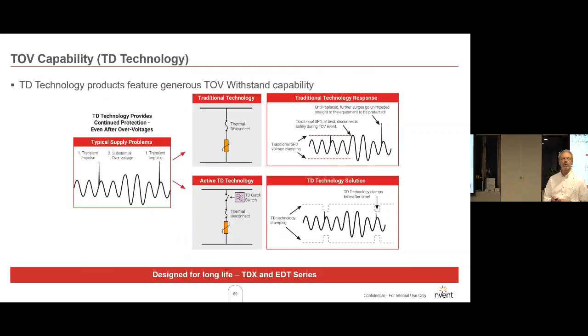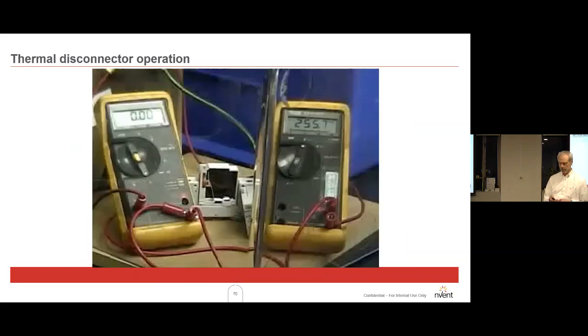We won't dwell any more on this today, except this was a slide showing one of the important things is thermal disconnect. So metal oxide varistors, when they get consumed, they'll go short circuit. So that's if a temporary overvoltage is there for a long time, or if they've just been working for a long time and consumed a lot of surges. In the old days, early days of MOVs, they would then catch fire. So you do see, I've seen one or two people wanting them to be in boxes, metal boxes, because that's what they've experienced in years gone by. That doesn't happen, I would say, to any surge diverter on the market these days because they've got internal fusing.